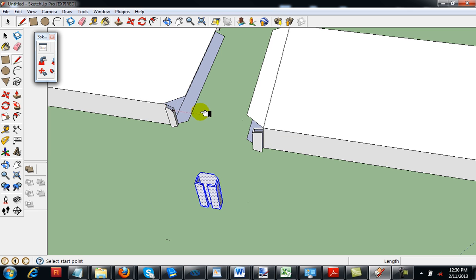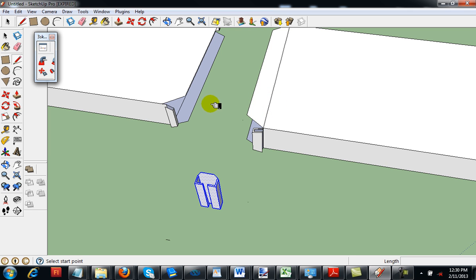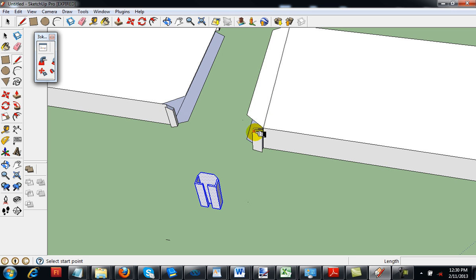What we do is we push the ductwork together. We have an S cleat that's on top here. This thing here is going to slide into this S cleat. Then this and this channel are going to butt together. Then this guy here is going to slide over that channel.